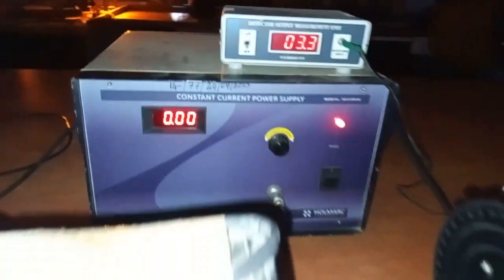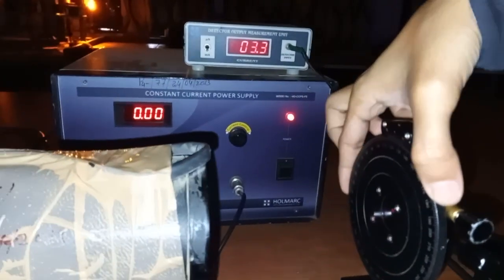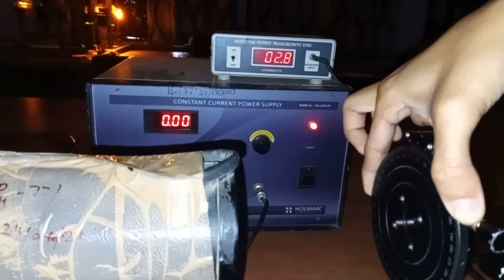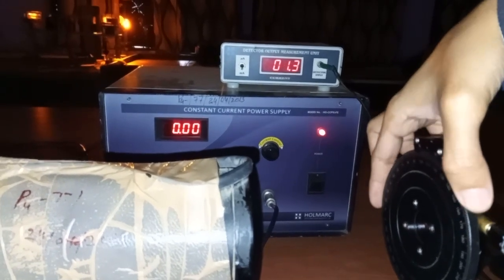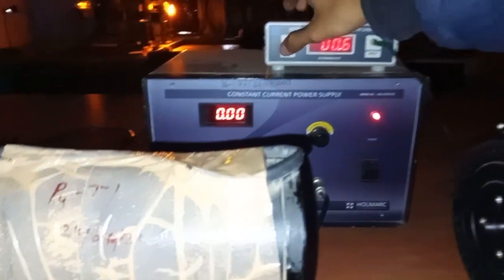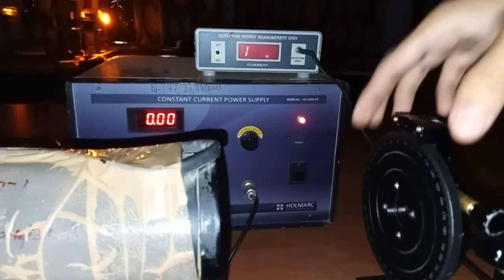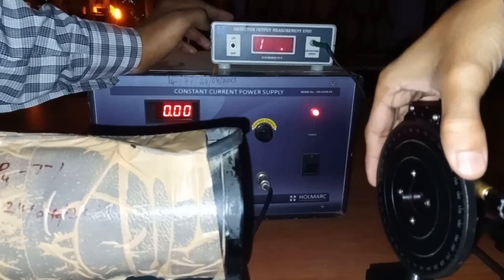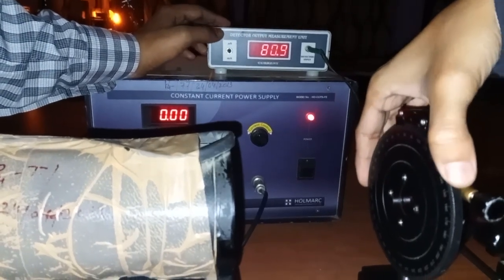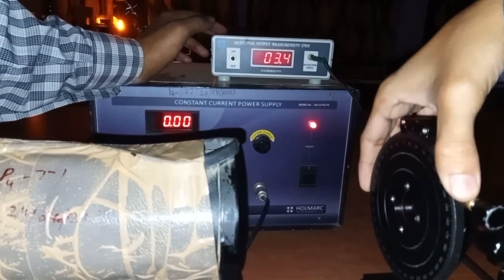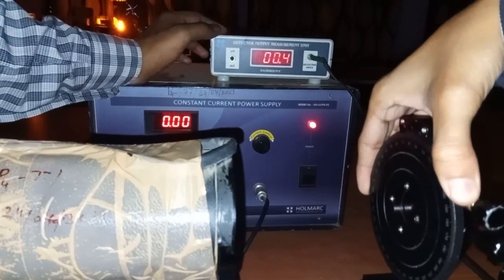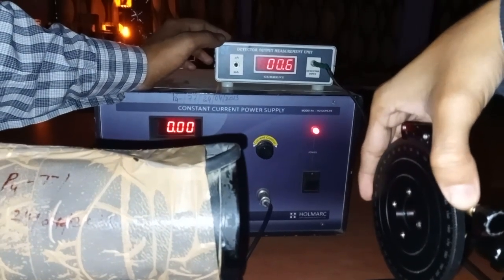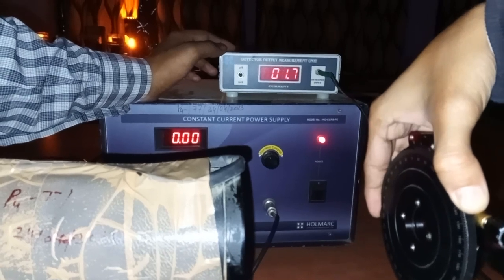So let's adjust it in this way to see the minimum current. First we have to make minima in milliamperes, then we have to set it in microamperes. We have to set minima. It should be almost nearly zero. As you can see, minima is around 0.5 or 0.4.